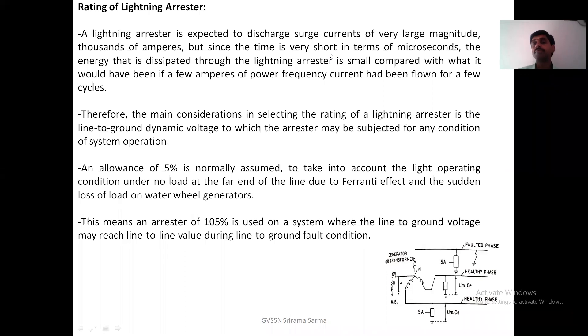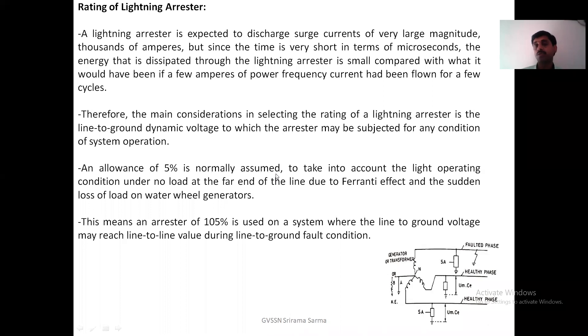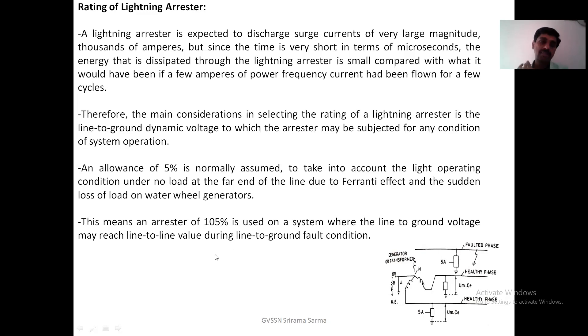That is why current is not taken for the rating purpose. Therefore, the main consideration in selecting the rating of the lightning arrester is the line-to-ground dynamic voltage to which the arrester may be subjected under any condition. An allowance of 5% is normally used to take into account the operating condition under no-load, because under no-load condition there is a 5% rise in voltage. This means an arrester rated at 105% is used on the system where line-to-ground voltage may reach line-to-line value during line-to-ground fault conditions.